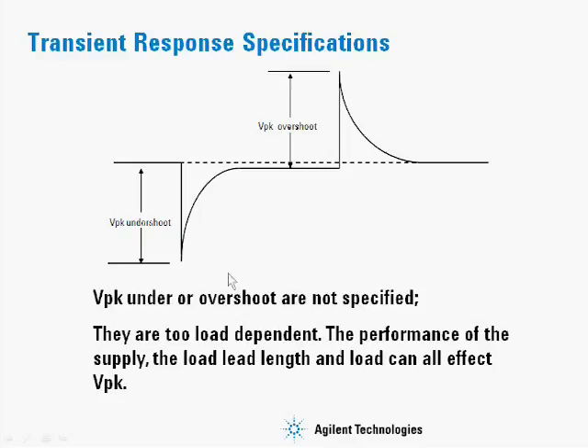There are other parts of the waveform that are not specified. Vpeak, undershoot, and overshoot are not specified, because there are too many variables that can cause these voltages to vary. The load lead length, the dressing of the leads whether they're twisted or not, and the load itself whether it's reactive can all affect Vpeak, overshoot, and undershoot. So you must be careful when attaching load leads to make them as short as possible and twist them together to minimize inductance.